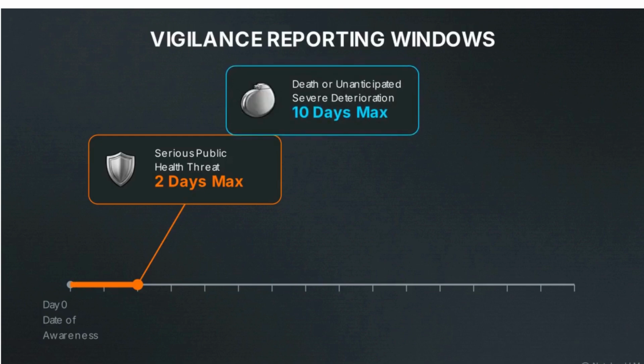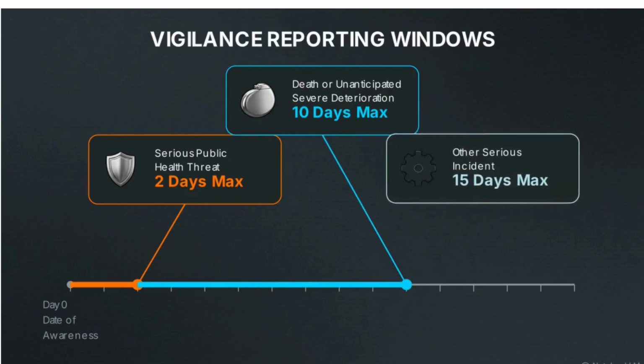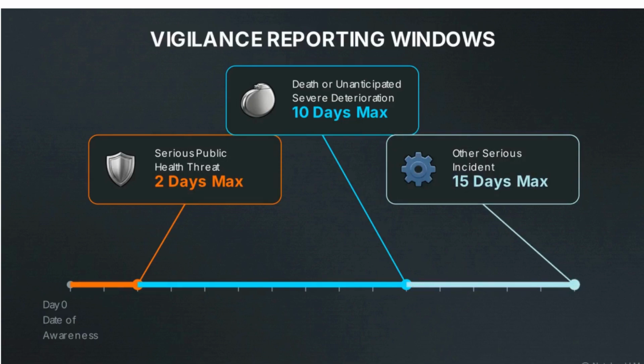If an incident involves a patient death or a sudden, unanticipated severe deterioration in a patient's health, that reporting window expands slightly, capping at 10 days. And for any other serious incident where a causal relationship to the device is established, the baseline requirement gives manufacturers exactly 15 days to investigate and report the event.